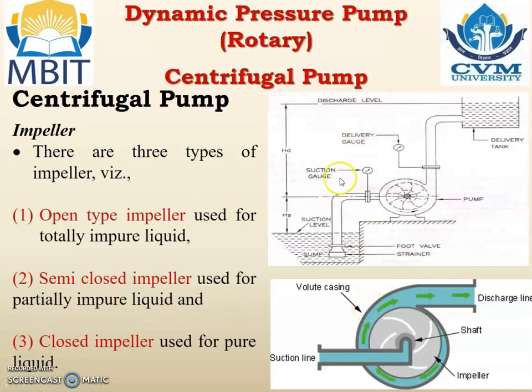There are three types of impeller. Open impeller, it is mainly utilized for the totally impure liquid. Semi-closed impeller, it is utilized for the partially impure liquid. And closed impeller, it is mainly utilized for the pure liquid.